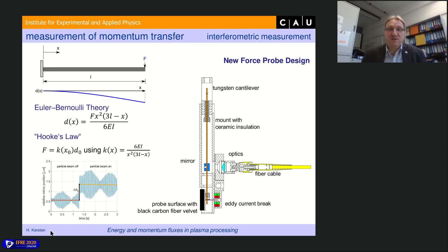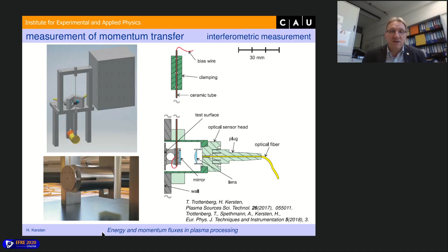So this is how it was constructed. There is still an eddy current damping, so that there are not too many oscillations, and we can determine the momentum. So we have here our plasma chamber. Here's the ion beam source, and here on the stage we have our instrument, the cantilever, and we can measure. We have two laser diodes to measure the interferometric signals in two directions. So we have an angular resolved force, so we can measure the force in both directions. If it is just perpendicular, then it's simple, but the ion beam could be under a certain angle, and then we measure the two components of the force here. As you can see here, here is one component, here's the other component, and the vector of the force can be decomposed into these components, and they are measured by the interferometers.